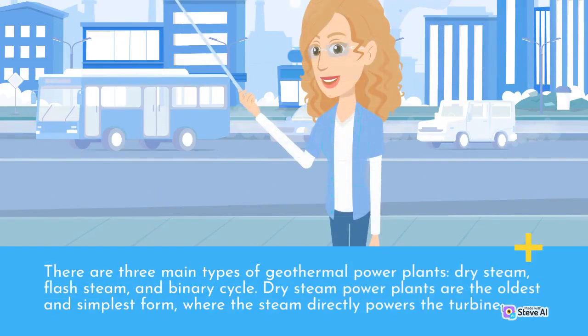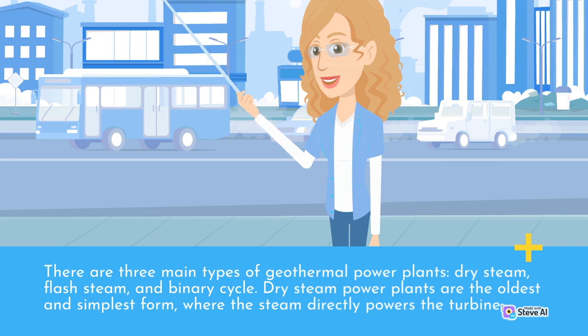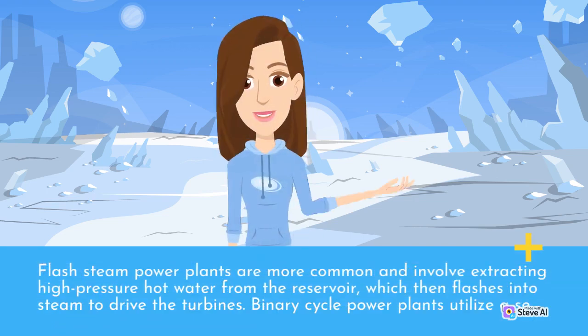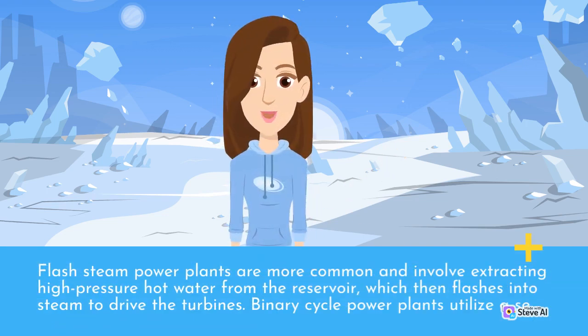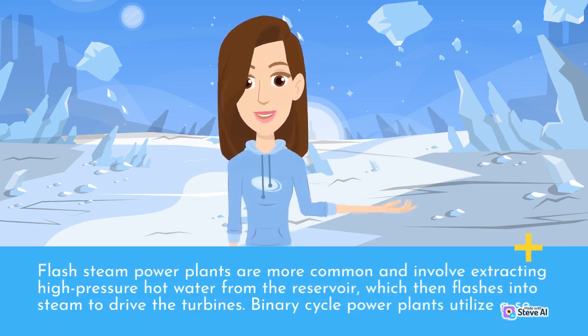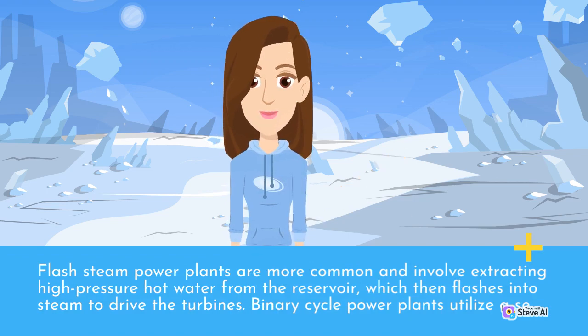There are three main types of geothermal power plants: dry steam, flash steam, and binary cycle. Dry steam power plants are the oldest and simplest form, where the steam directly powers the turbine. Flash steam power plants are more common and involve extracting high-pressure hot water from the reservoir, which then flashes into steam to drive the turbines.